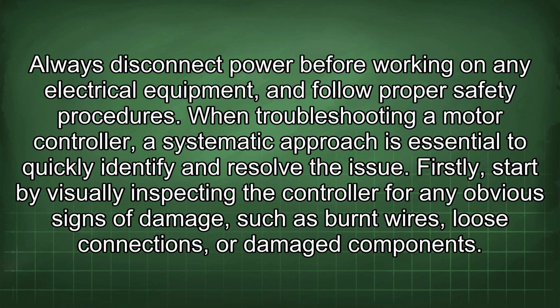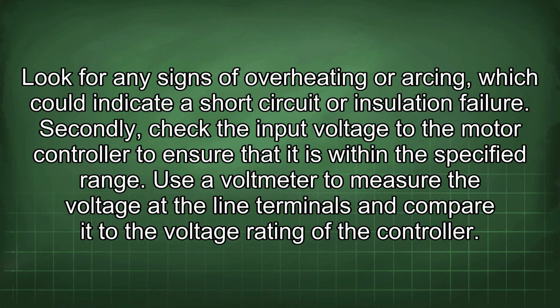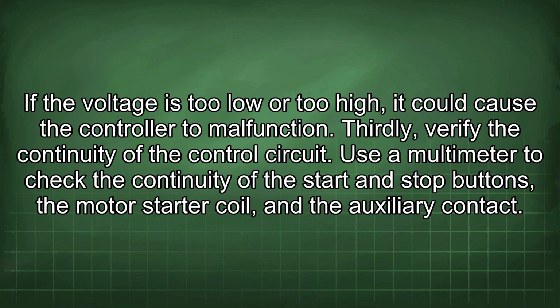When troubleshooting a motor controller, a systematic approach is essential to quickly identify and resolve the issue. Firstly, start by visually inspecting the controller for any obvious signs of damage, such as burnt wires, loose connections, or damaged components. Look for any signs of overheating or arcing, which could indicate a short circuit or insulation failure. Secondly, check the input voltage to the motor controller to ensure that it is within the specified range. Use a voltmeter to measure the voltage at the line terminals and compare it to the voltage rating of the controller. If the voltage is too low or too high, it could cause the controller to malfunction.